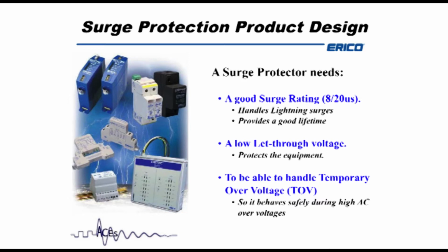That premature aging I was talking about is caused by what we'd know as a temporary overvoltage - a 50 hertz overvoltage, maybe for a few cycles or a bit longer, that exists on that input feed. And that, I can tell you right now as a surge protection engineer, is death to the metal oxide varistor. It kills it very quickly. It's designed to handle very short durations, not 50 hertz overvoltages.